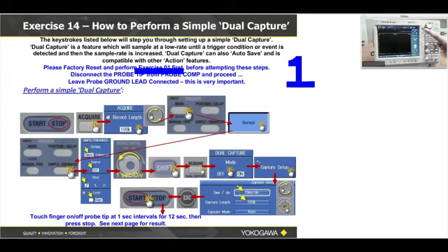Nothing happens at this time, but I've got a 10-second nice slow acquisition here. There's nothing on my probe. There's no noise. But now when I expose the tip here, I can pull this tip off, and I can touch it, and I create a capture. I hope you guys can see that on the video. I'm going to hit it about 6 times. Make sure you're getting the same response as my instrument here.